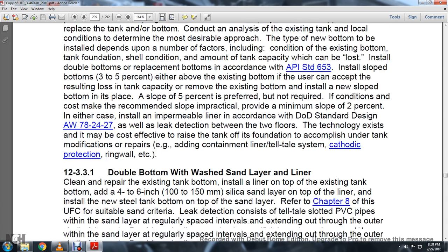12331 Double bottom with washed sand layer and liner. Clean and repair the existing tank bottom, and install the liner on top of the existing tank bottom. Add a 4 to 6 inch silica sand layer on top of the liner and install the new steel tank bottom on top of the sand layer.